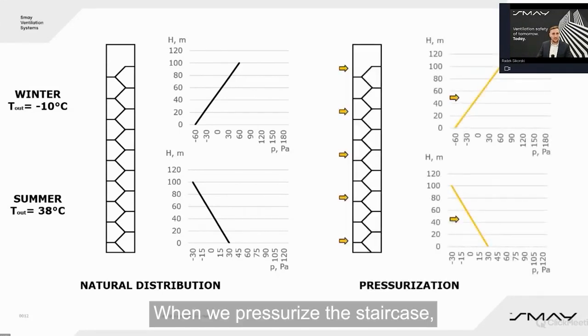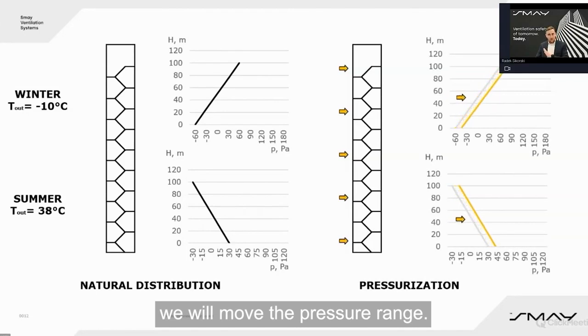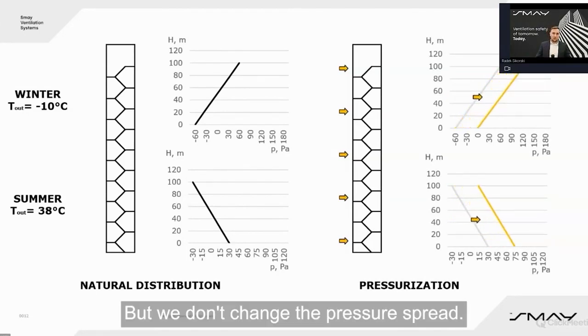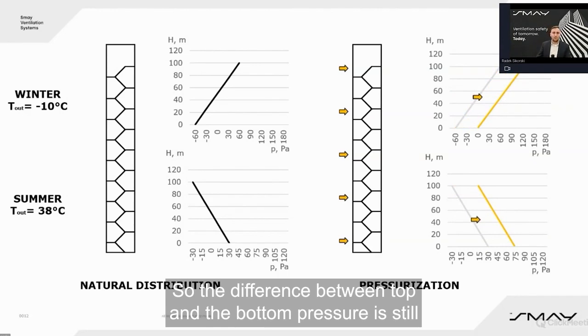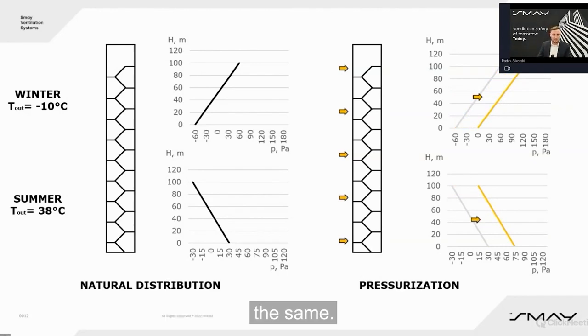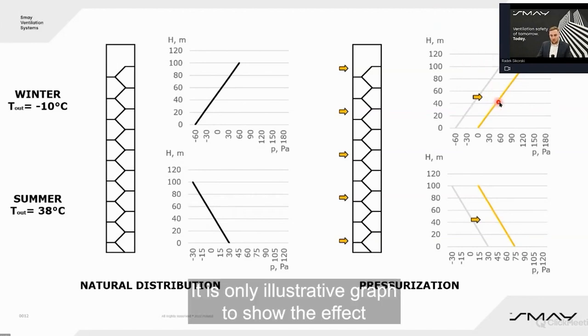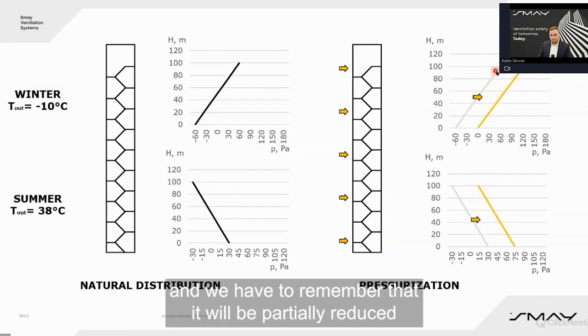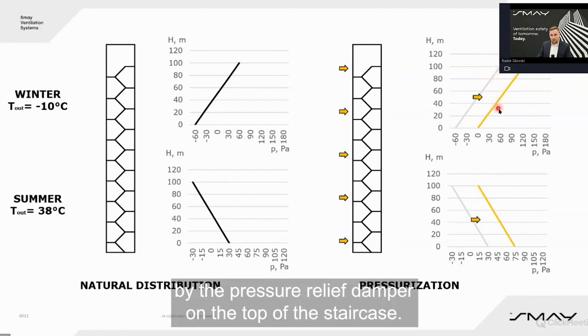When we pressurize the staircase, we will move the pressure range, but we don't change the pressure spread, so the difference between the top and bottom pressure is still the same. This is an illustrative graph showing the effect, and we have to remember that it will be partially reduced by the pressure relief damper on the top of the staircase.